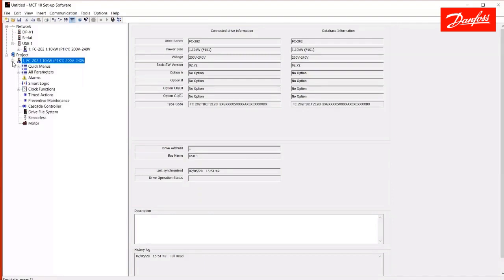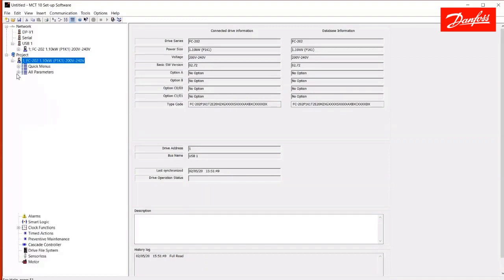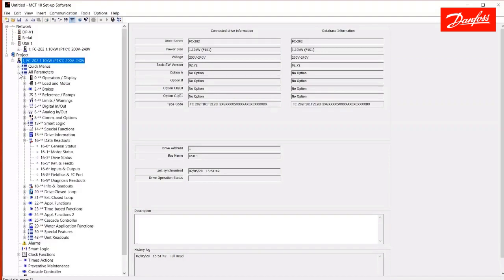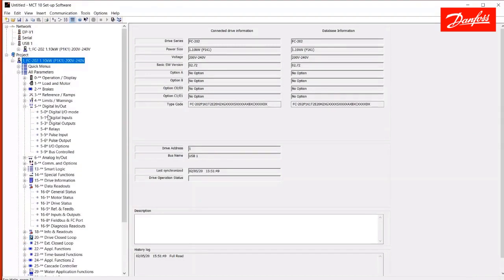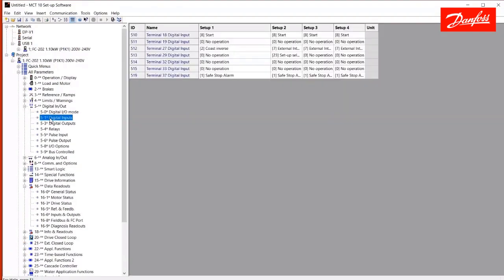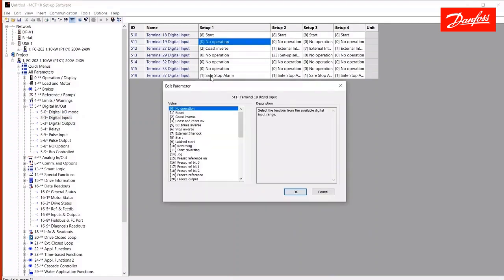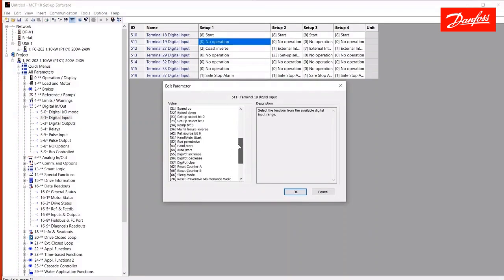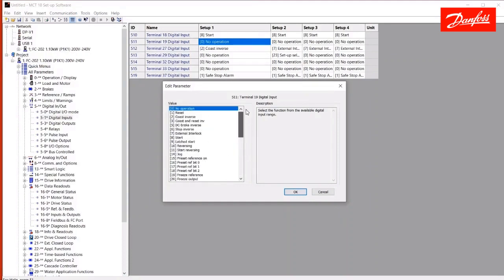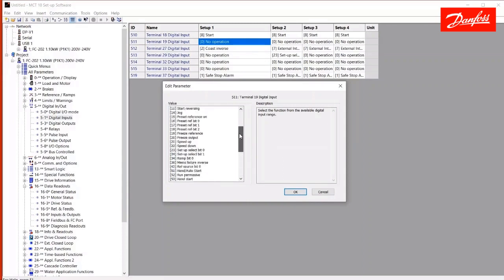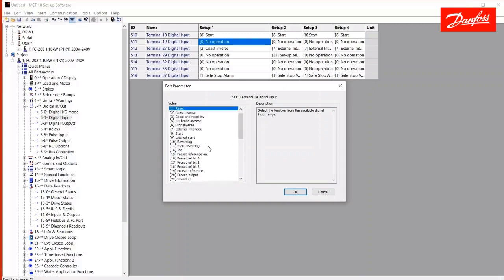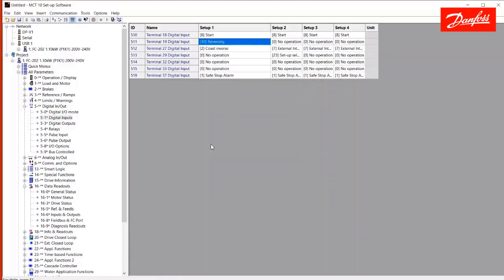Like I mentioned earlier, you can save drives on the project side. So I'm going to go ahead and make a simple change here to digital input terminal 19 on the project side. I'm going to change this to the value no operation. I can scroll up and down here. Sorry, I'm going to change this to the value reversing. I can scroll up and down and find that and use my mouse here. Or I can also use hot keys. So I'm going to hit the R key on my keyboard, and you'll see it will jump right to all the words starting with the letter R. And then I can use the enter key.